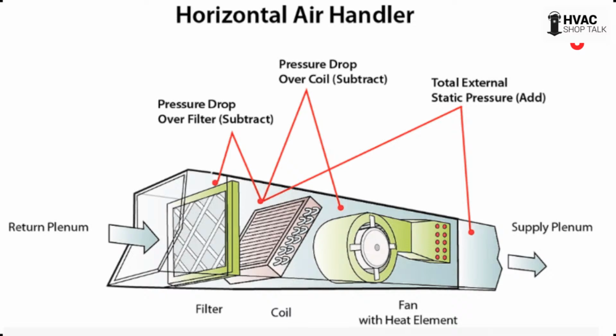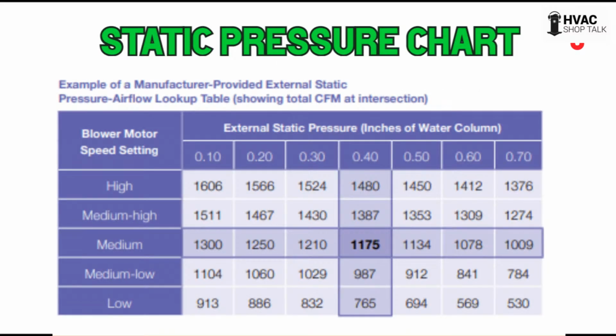We're going to go on to the actual static pressure chart. This is an example of what it might look like here on the screen. Basically, you go to the back of your installer's manual, and you'll find charts with various blower speeds and different external static pressure measurements. You'll line up both things you measured, or the one thing you've measured, which is the external static pressure, and crisscross it with whatever speed you've chosen. You'll see on screen here that this particular one is medium blower tap, 0.40 total external static pressure, and it shows 1175.